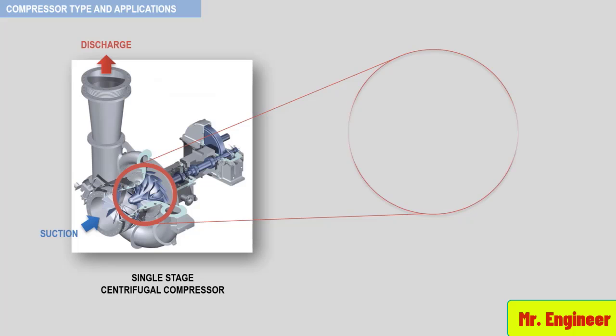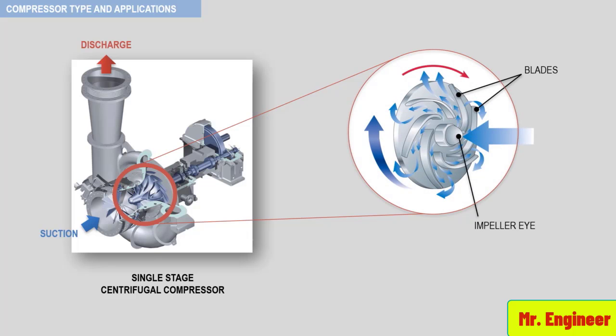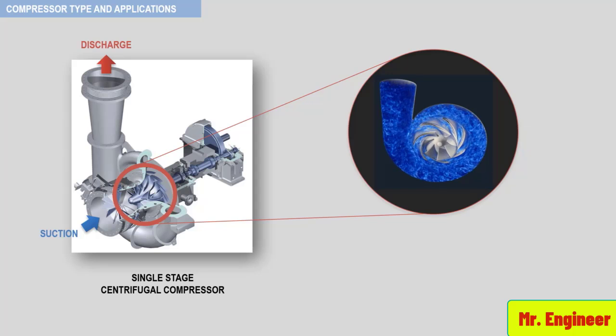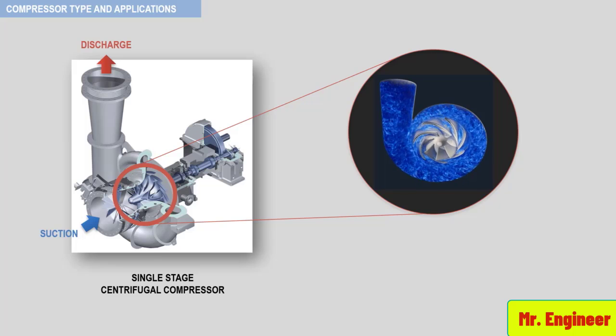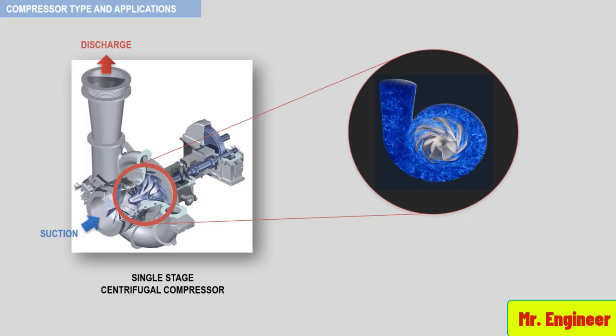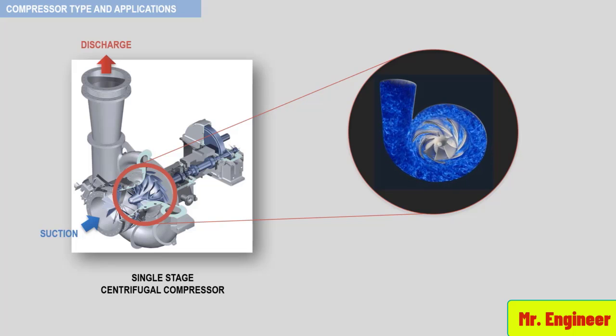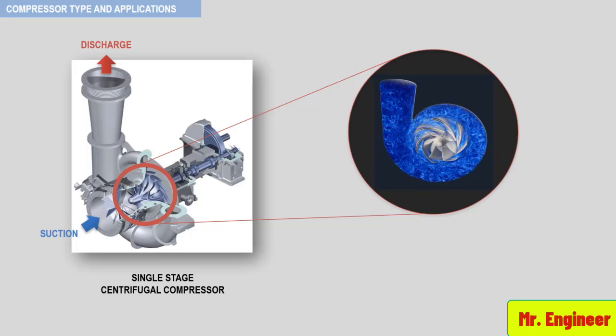The following figure shows a simplified sketch of the gas path across the impeller, and here a simplified animation to better illustrate this concept. What I want you to remember is that the flow from a centrifugal compressor is mostly governed by the speed of the driver and the height of the impeller blades. The pressure or head that the compressor can generate is mostly governed by the speed of the driver and the diameter of the impeller. Other factors play a lesser role, like the number, pitch and thickness of the impeller blades, and the internal clearances. We'll see this in detail further ahead.